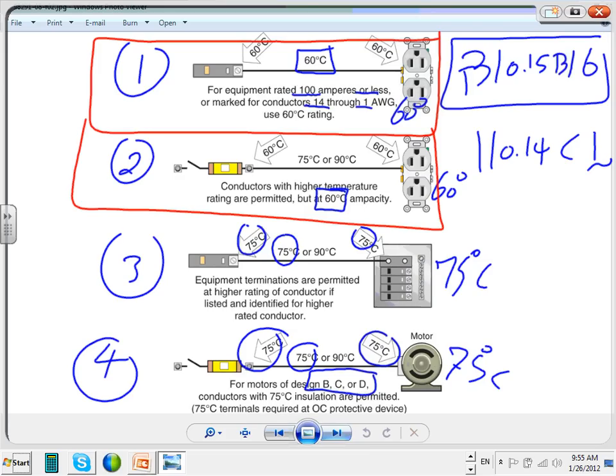Suppose that this is 75, this is 75, and Nick decided to use a 60-degree rated cable here. Look at this. I decided single-handedly to use a TW, 60-degree rated cable between lugs that are rated 75. Can I continue to use 75? No, they call it the weakest link. The cable has to be 75, and the two lugs on both sides have to be 75 for you to use 75. If you don't know the terminals when we start, here's your default.